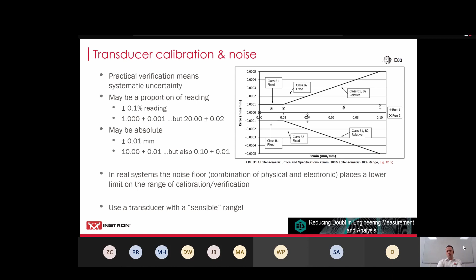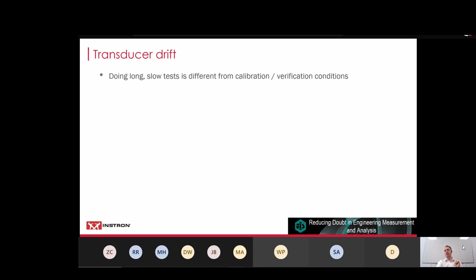Now, this is all very good about straightforward calibration and verification. However, when we start talking about fatigue tests especially, they become long and they become slow. Calibration or verification conditions are realistically minutes or maybe an hour or so. We are often doing tests where a fatigue test will run for many hours, if not many days. And there are things that can creep in where you can get drift happening in the transducer due to environmental changes, especially. This is most significant where the temperature changes.